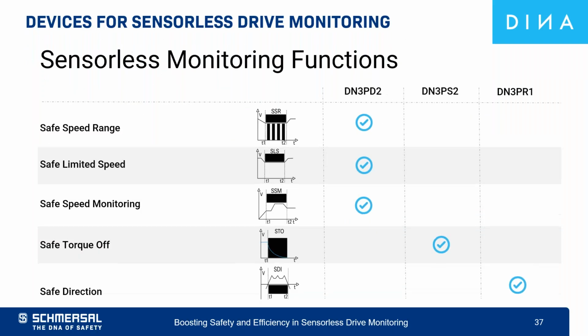Okay, and finally, I have a comparison of the sensorless monitoring functions which each device can do. In this overview, you see the speed monitor DN3PD2 can do safe speed range, safe limited speed, and safe speed monitoring. The standstill monitor DN3PS2 can do safe torque off, and the rotational direction monitor DN3PR2, PR1, again the same mistake, sorry for that, can do safe direction. That's it about the units.